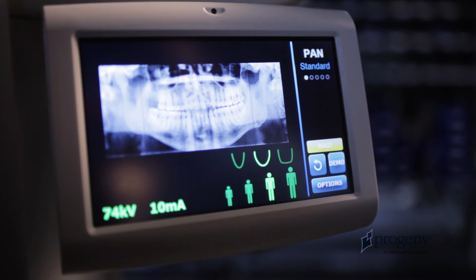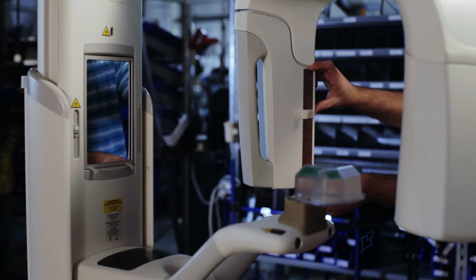In order to visualize the image phantom properly, select 66 kilovolts and 8 milliamps during X-ray scans. Place the copper strip over the sensor as further beam attenuation. Firmly place the phantom on the positioning table. The position of the image phantom should leave no gaps between the phantom mounting block and the patient table casting. Activate the alignment lasers and center the cuspid laser.